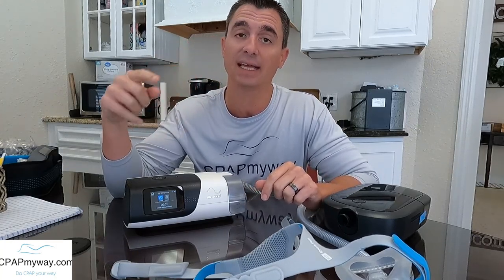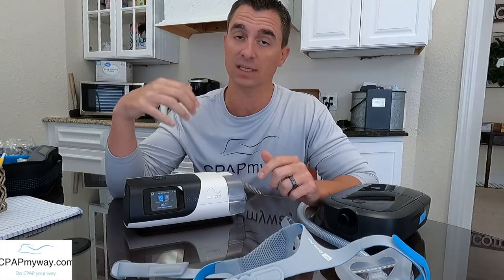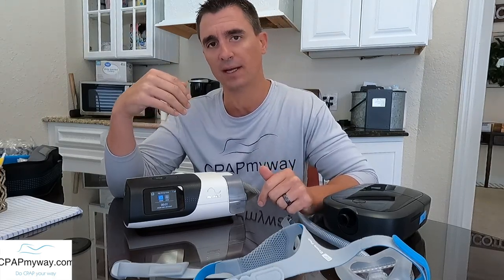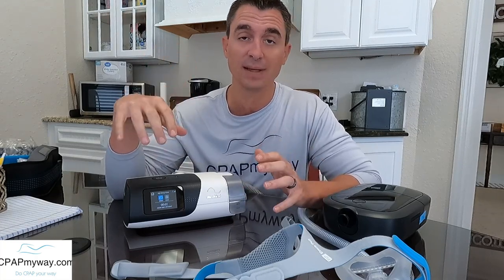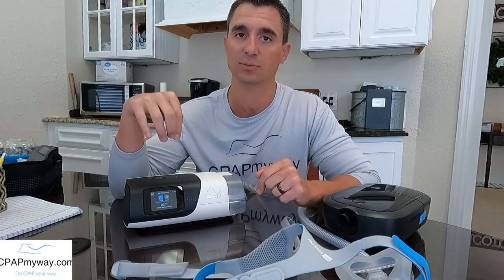What happened there is I was demonstrating your mask bumping up against your pillow and some air leaking out of the side of the mask. The machine believes that you have taken your mask off and that it needs to shut itself down — it has an auto-off feature. What we hear from a lot of people is that it turns off and then turns back on, and that's because it also has an auto-on feature. When it senses you breathing again, it'll kick the machine back on. So it can turn on and off seemingly on its own, which would seem like a malfunction, but it is actually a feature inside this machine.